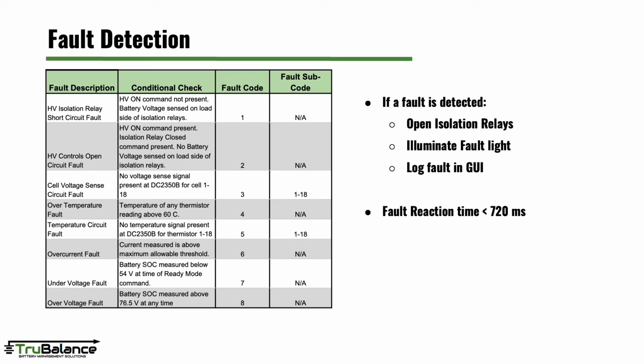Detectable faults include high voltage open circuit and short circuit conditions, overcurrent in the high voltage system, over temperature, over voltage, and under voltage. When any of these faults are detected, they are displayed on the GUI and a fault light is illuminated through GPIO control. Additionally, faults will immediately deactivate the isolation relay circuits.